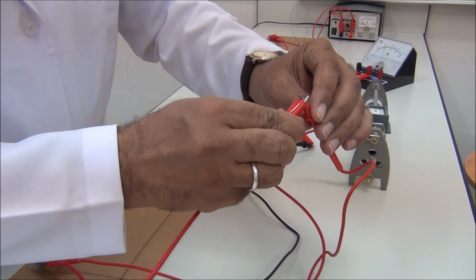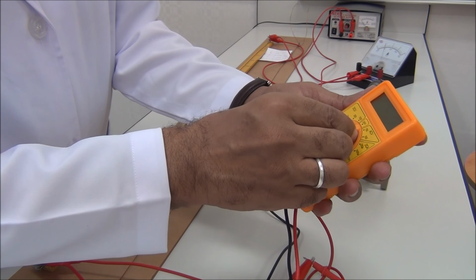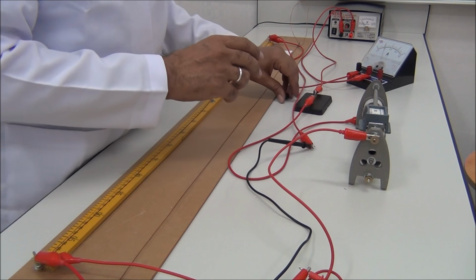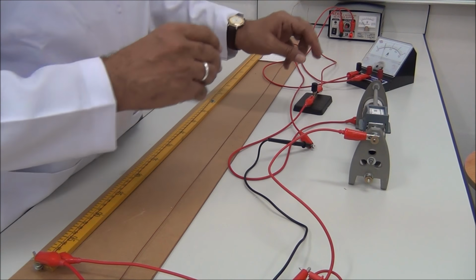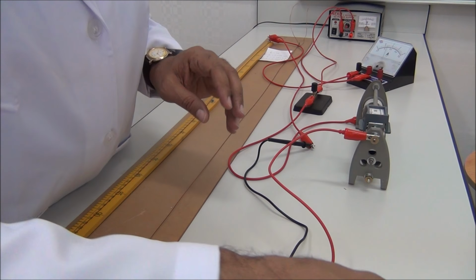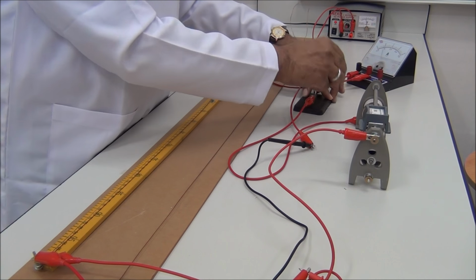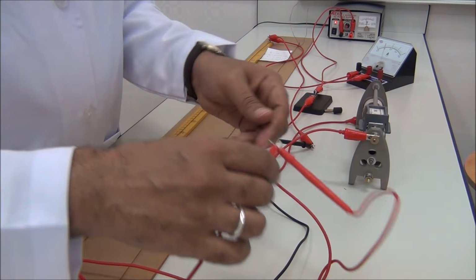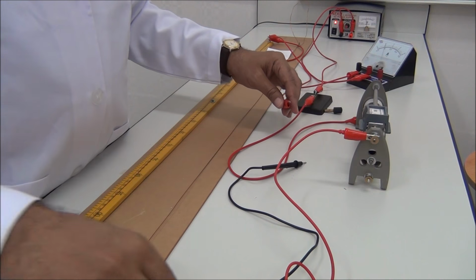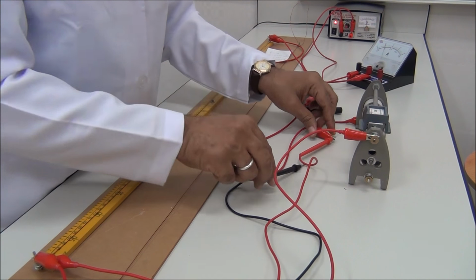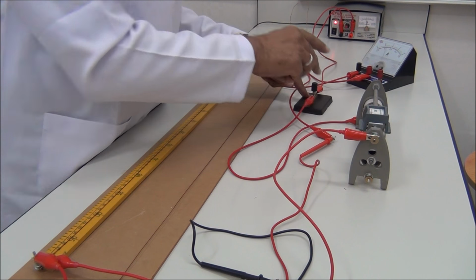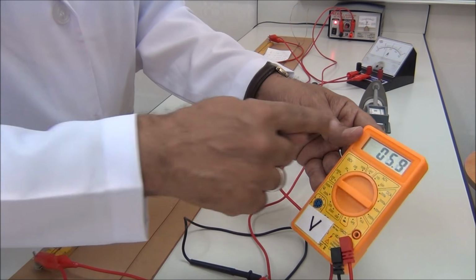This one. Now we adjust the millivoltmeter, it's digital. Okay, and now we check again, switch on. Oh, it is negative, so we just exchange the wires. This wire, exchange it, so this one here and this one here. And we check again. Yes, it's working, with a positive value.